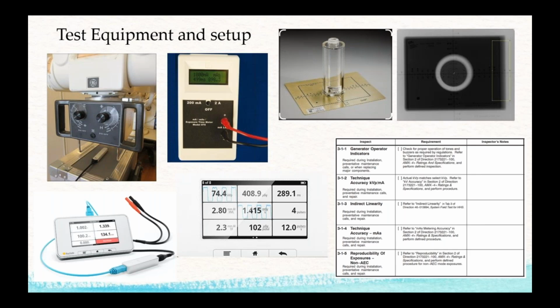And as you know from troubleshooting in electronics, to accurately measure mA, I have to be in series with the wiring. So there's usually a circuit board somewhere in the generator with a jumper plug on there. You have to pull the jumper plug up. Another reason I carry the X2 around is that with a special cable, I pull that jumper plug and I can actually measure mA. I don't need a separate meter.